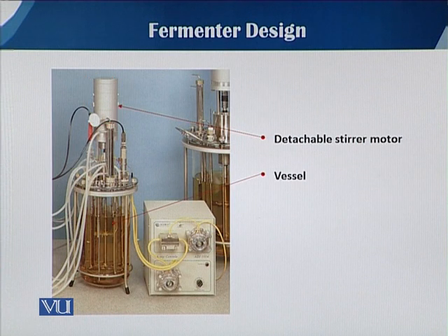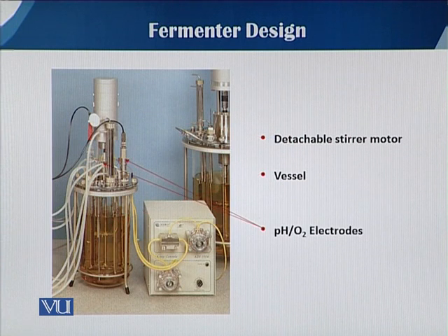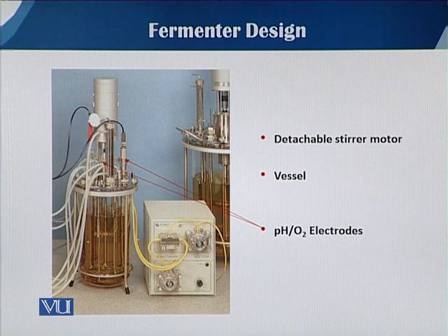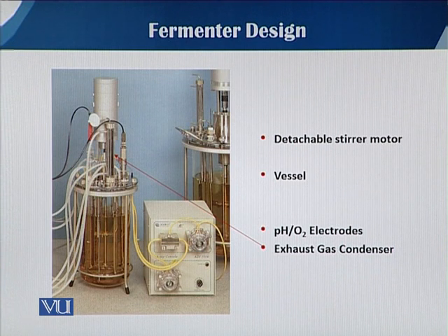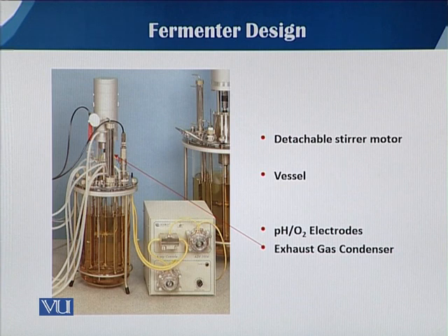You can see that this vessel is known as the body vessel, and on the upper plate there are different electrodes — a pH electrode, an oxygen electrode — and then there is a condenser from where the gas exhausts. When we have the aeration supply, the air has to exhaust, and to minimize evaporation loss we fix the condenser over the fermenter. That is why it is known as the exhaust gas condenser.